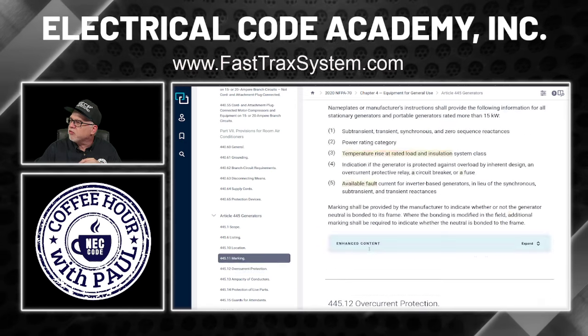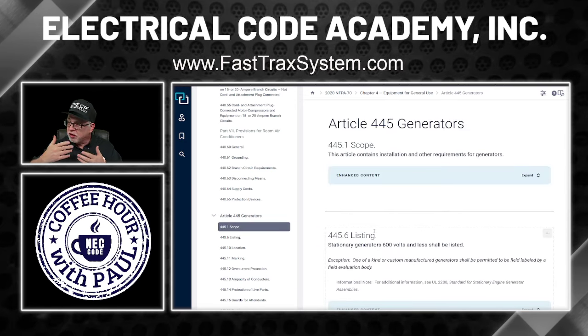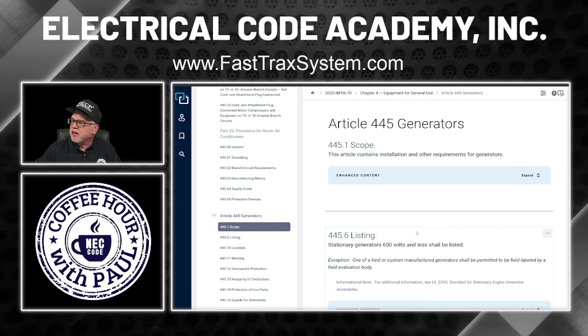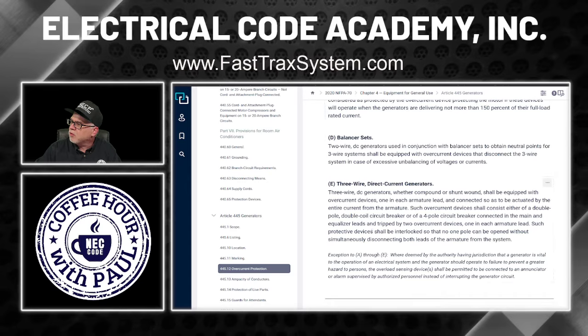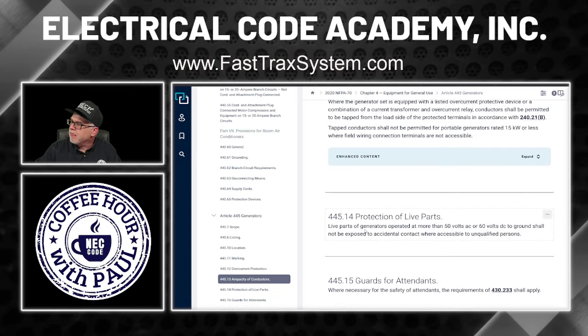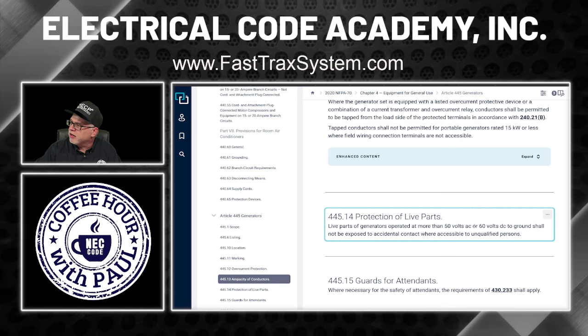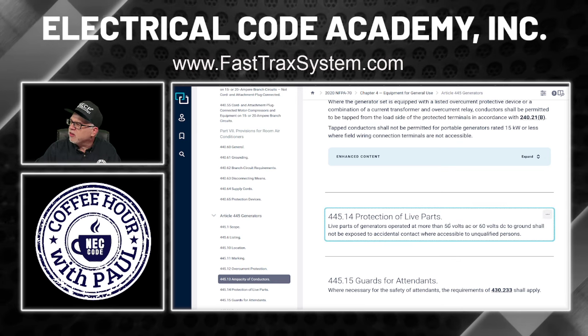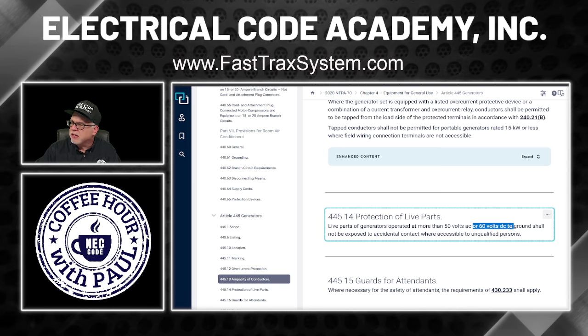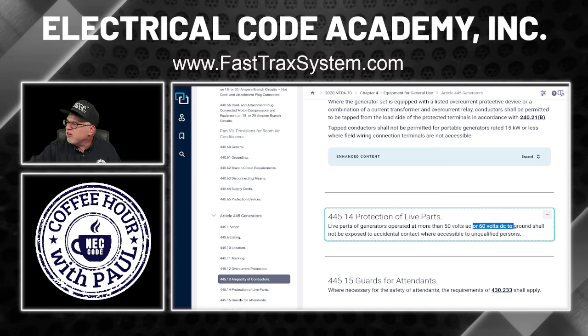Now, if I was bold scanning this and just went right to 445 because I knew that it was a small article, I'm bold scanning for the live parts. So I'm looking here, and I'm going down. And boom, right there, live parts. And I see the triggers in here. There's voltage classes. Now, immediately I notice you're saying, well, Paul, how do you know it's not 50 or 60? Well, if you look in the question, it says 50 for AC, 60 for DC.